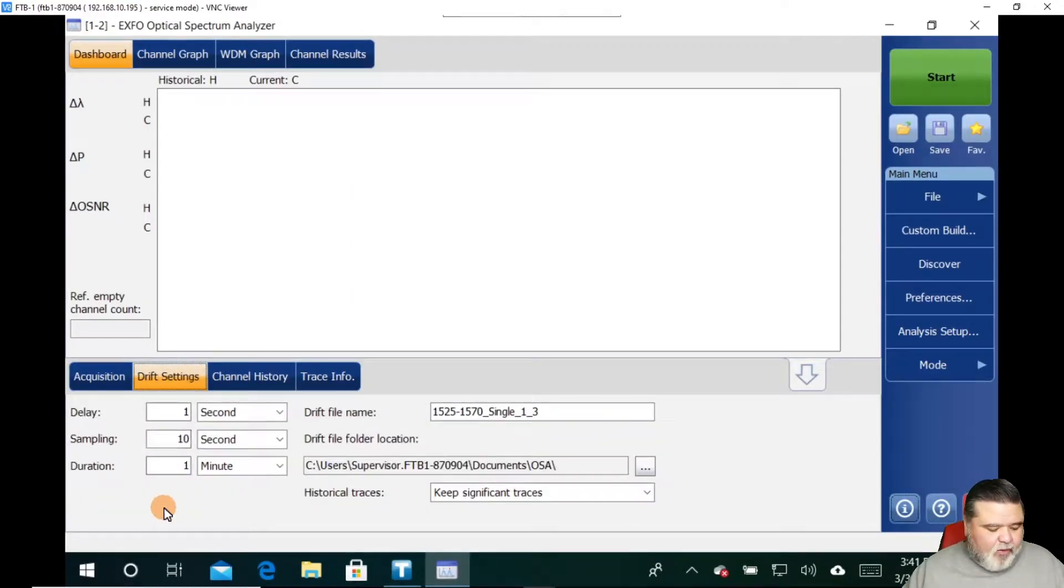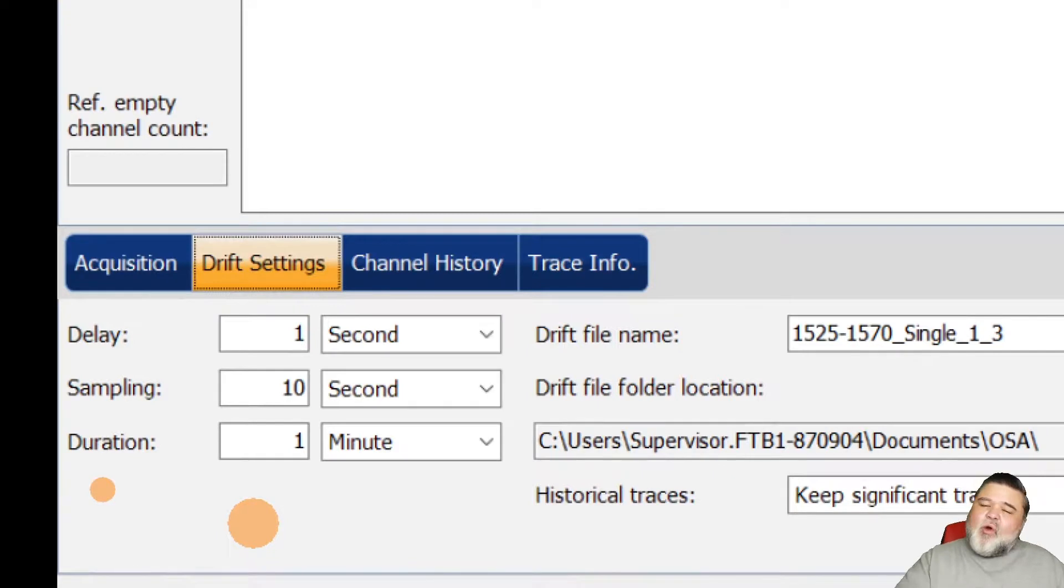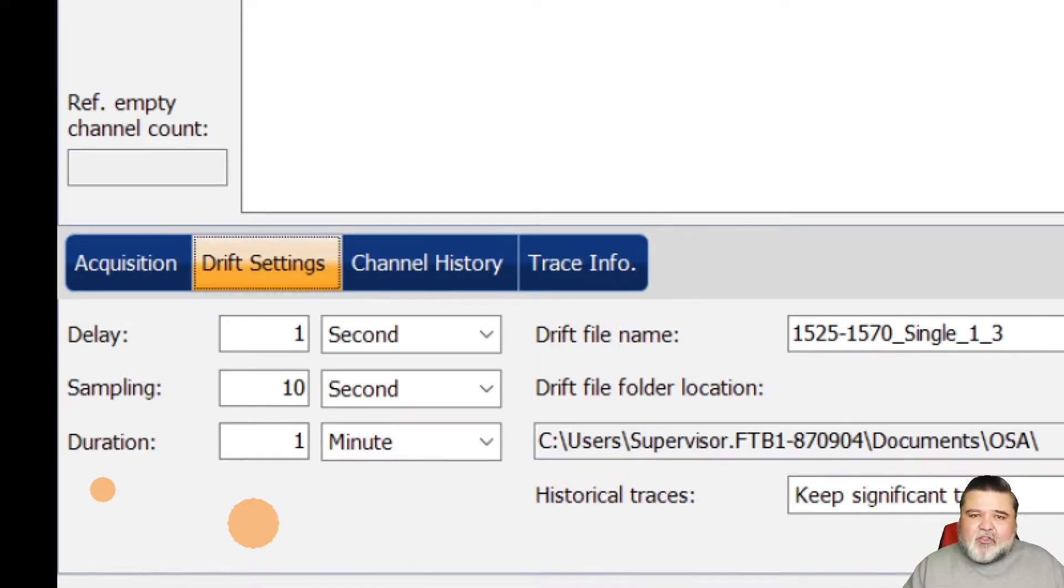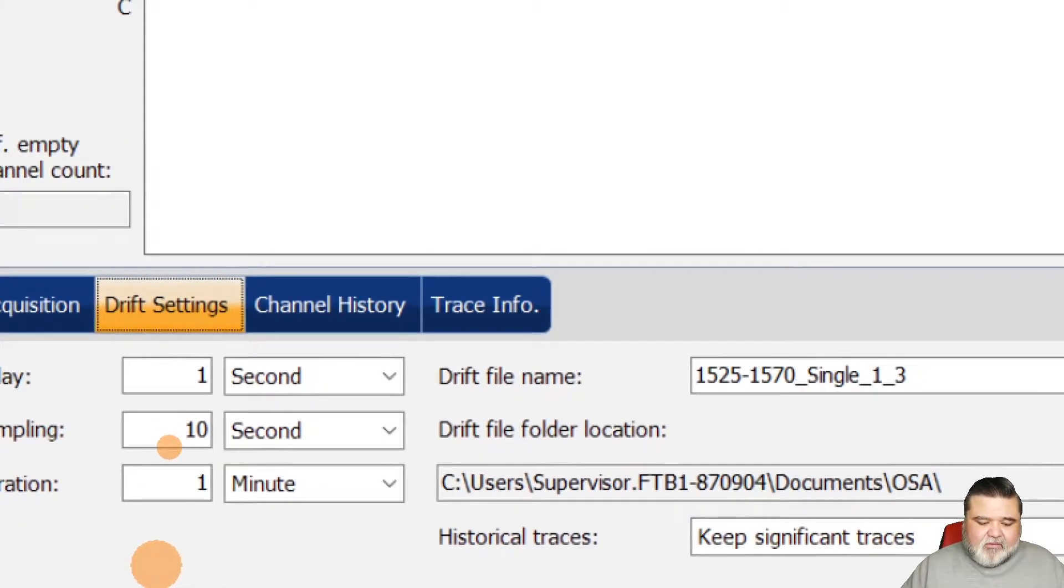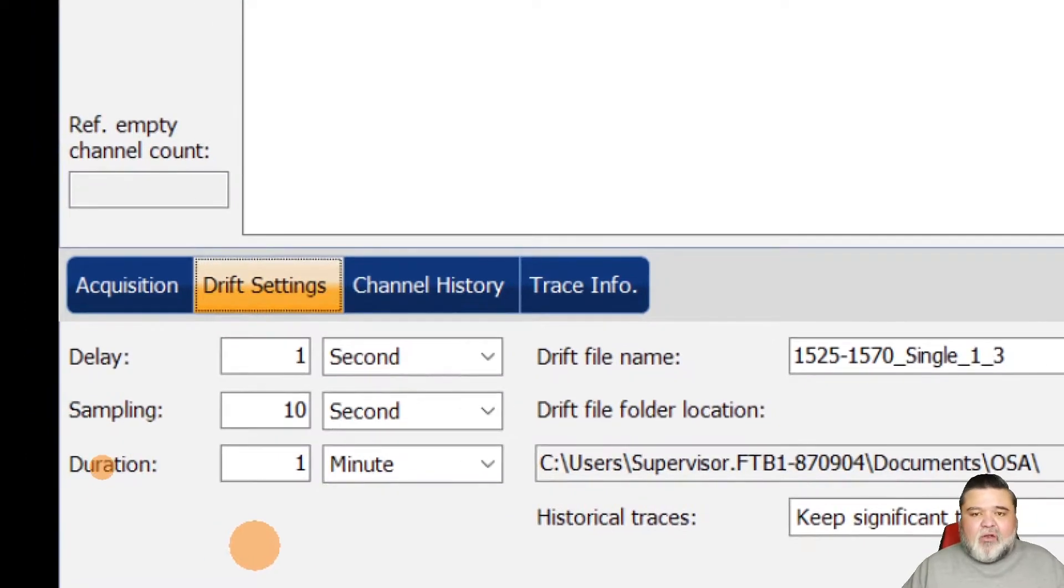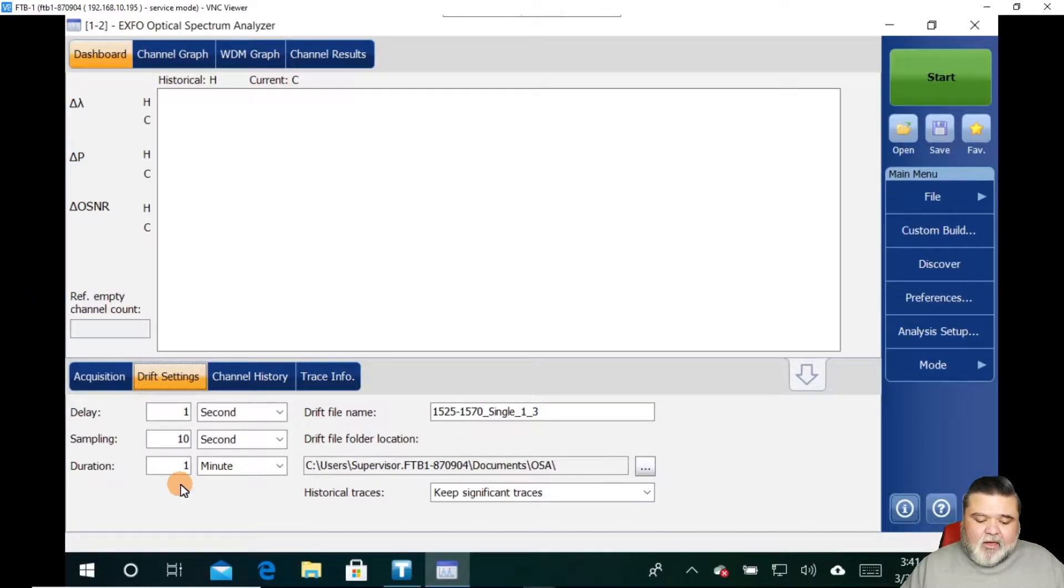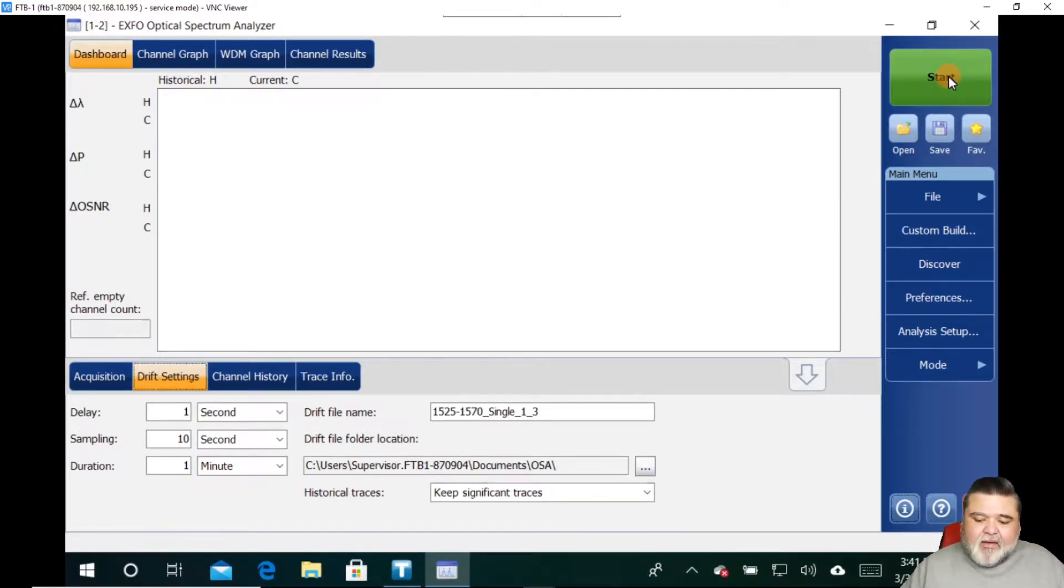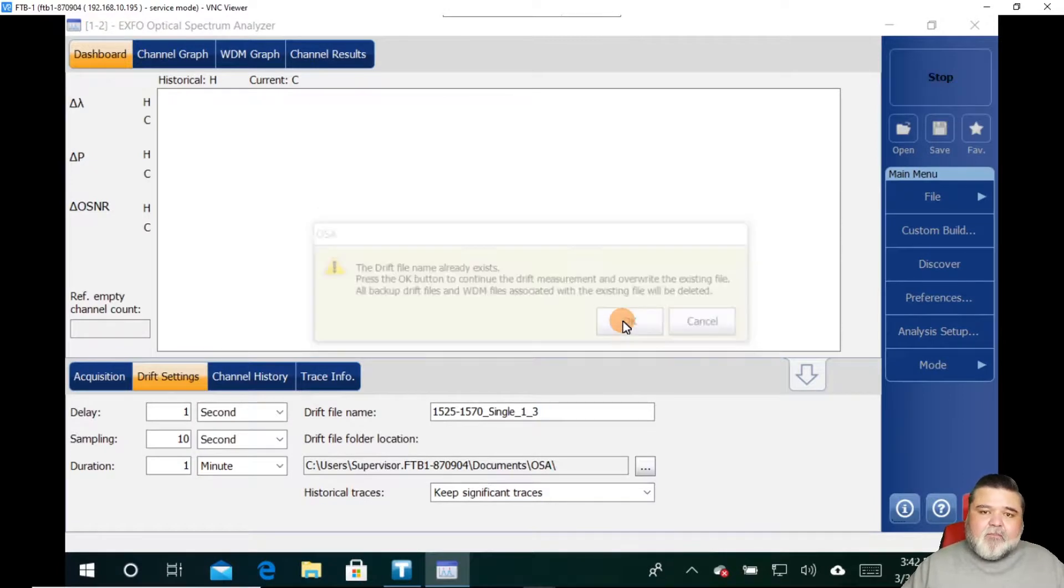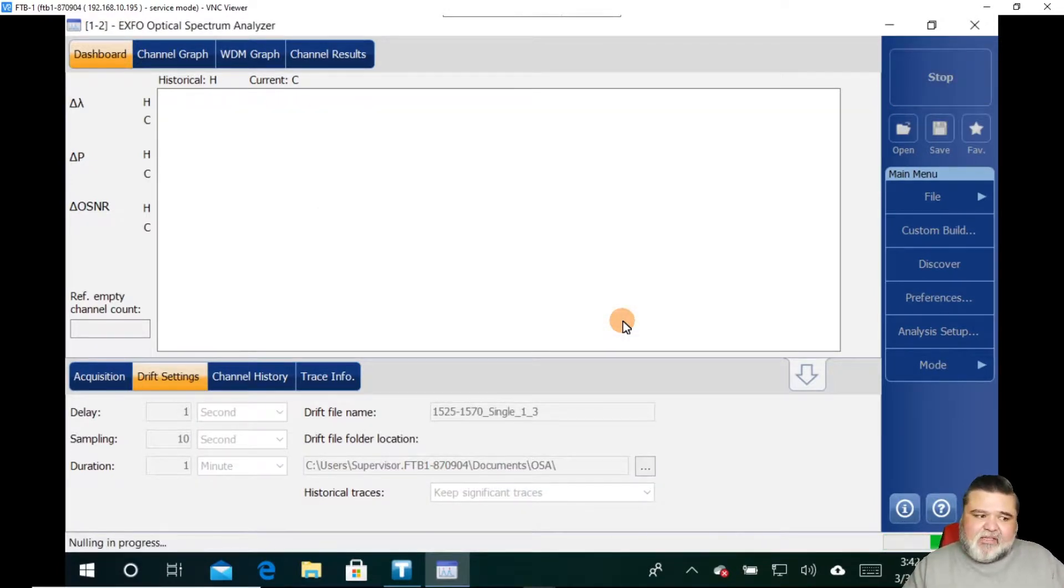Essentially I'm going to do one single acquisition, but I need to set some drift settings. The three primary settings are: delay, so after I hit start, when do you want me to start doing the test? If you want it to start in 12 hours in the middle of the night, you can do that. How often do you want it to test? This one's every 10 seconds. And for how long? One minute. Obviously you would use longer settings than this, maybe 24 hours, maybe 12 hours, whatever. In this example, I'm just going to do that.